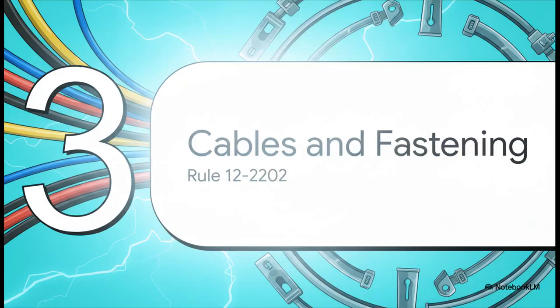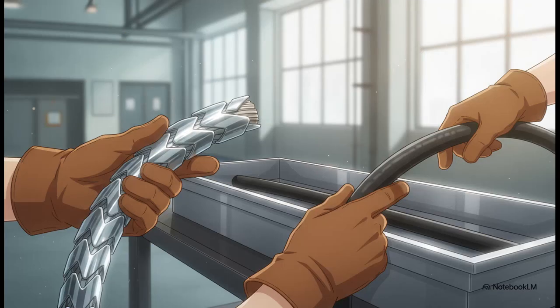All right, Section 3, Permitted Cables and Fastening. So, we've built the tray. Now, what are we actually allowed to put in it? We're looking at Rule 12-2202. The standard requirement is honestly pretty straightforward. Cables for use in trays generally need a continuous metal sheath or interlocking armor. But there are some major industrial exceptions.